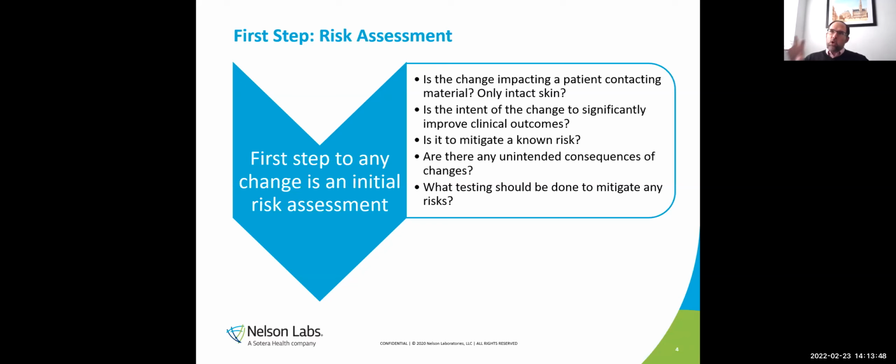So if you have a tool, like a delivery device or a surgical tool that has a fluid path that runs saline solution or contrast solution or something through it, and you're changing a portion in the handle that has that fluid path, that's a patient-contacting portion. That means it's more concerning than if you're changing, for example, the handle of the device that the surgeon holds onto.